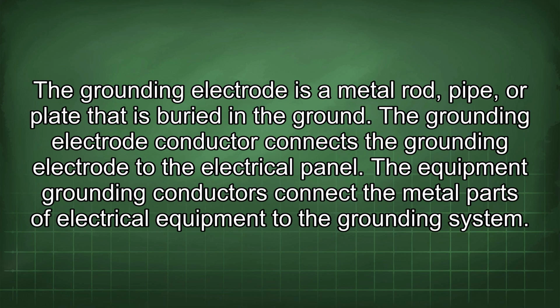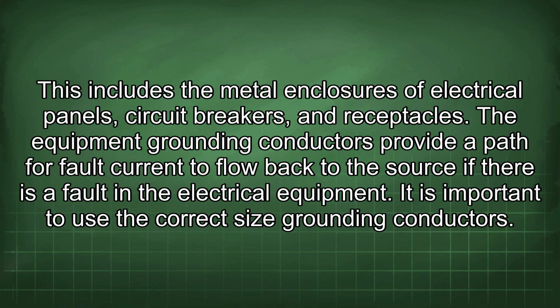The grounding electrode is a metal rod, pipe, or plate that is buried in the ground. The grounding electrode conductor connects the grounding electrode to the electrical panel. The equipment grounding conductors connect the metal parts of electrical equipment to the grounding system. This includes the metal enclosures of electrical panels, circuit breakers, and receptacles. The equipment grounding conductors provide a path for fault current to flow back to the source if there is a fault in the electrical equipment.